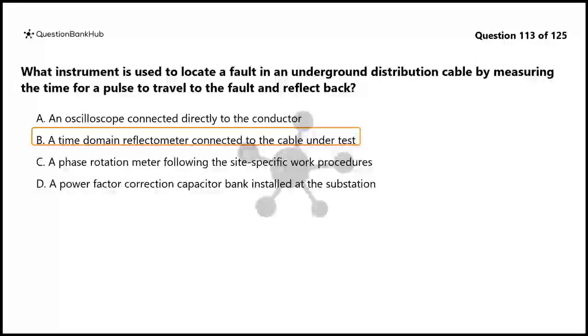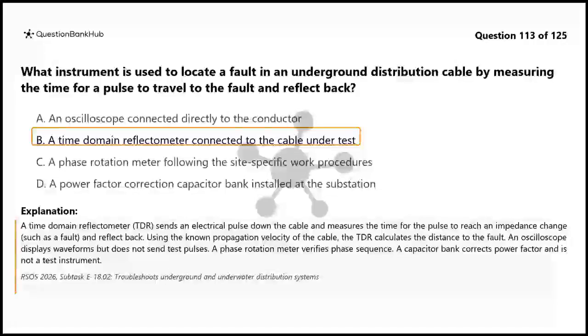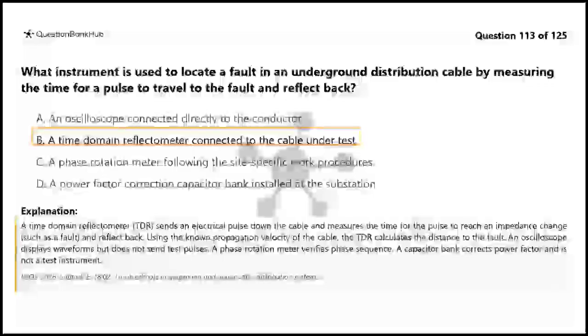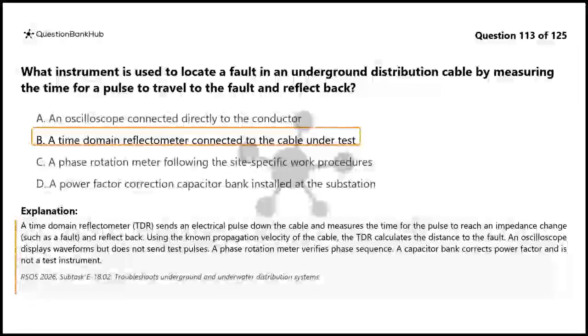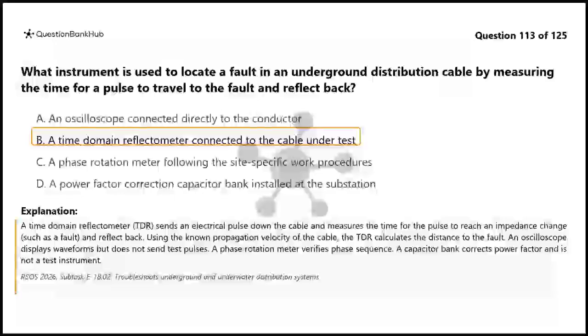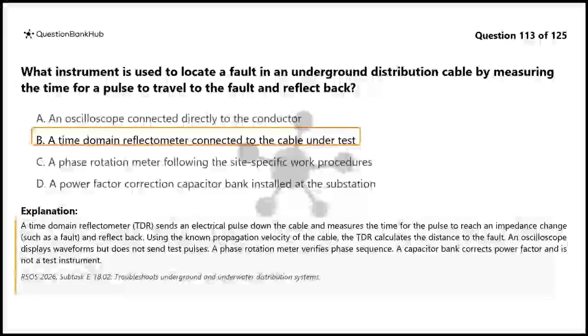The correct answer is B. A time domain reflectometer, TDR, sends an electrical pulse down the cable and measures the time for the pulse to reach an impedance change, such as a fault, and reflect back. Using the known propagation velocity of the cable, the TDR calculates the distance to the fault. An oscilloscope displays waveforms but does not send test pulses. A phase rotation meter verifies phase sequence. A capacitor bank corrects power factor and is not a test instrument.